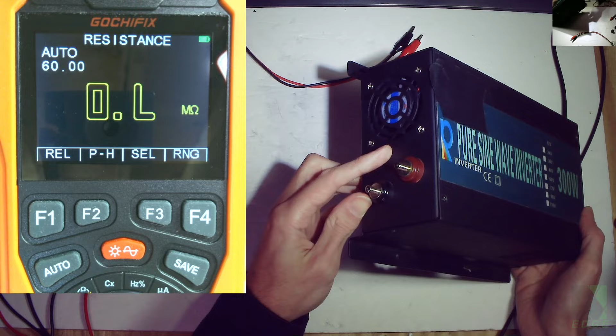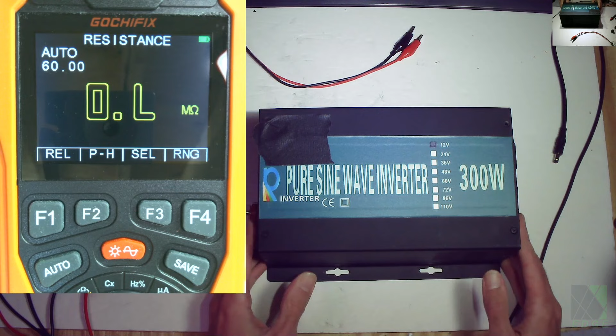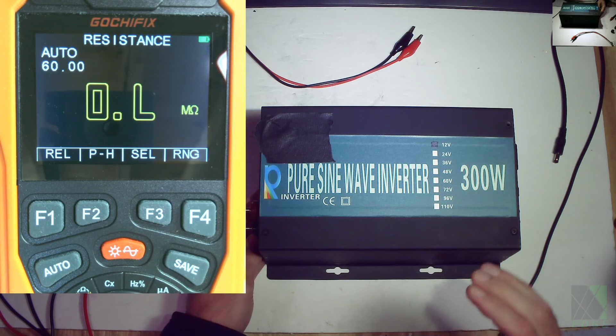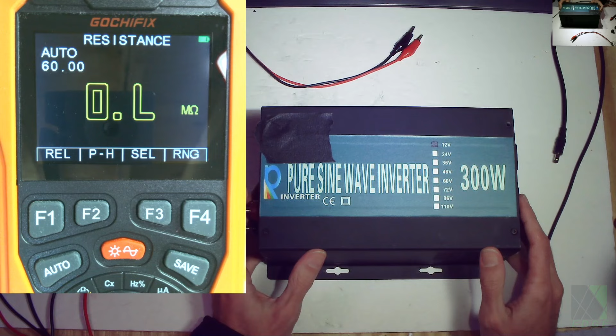Some inverters will have the fuses on the back. This particular model doesn't. This particular model, you have to open it to see any fuses that are inside of it. Some inverters have the fuses soldered down to the circuit board inside. Those are a real pain. Some of them have sockets, and you can just replace the fuses. However, before you do that, if the fuse blew, then something went wrong, and replacing the fuses probably isn't going to fix it.